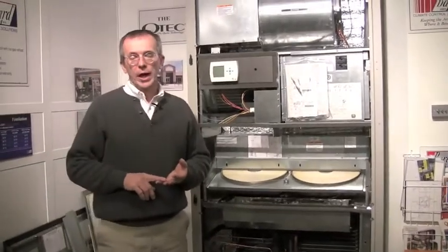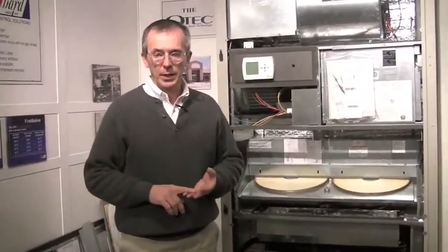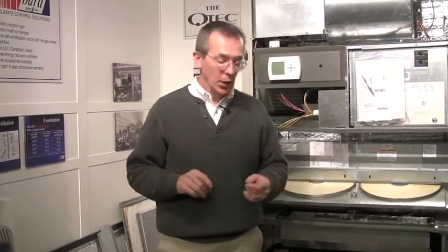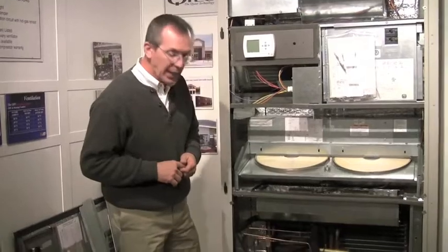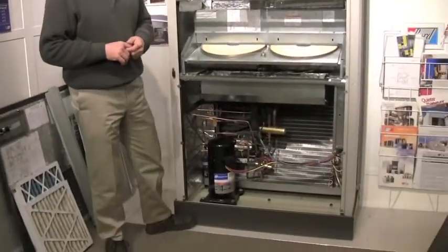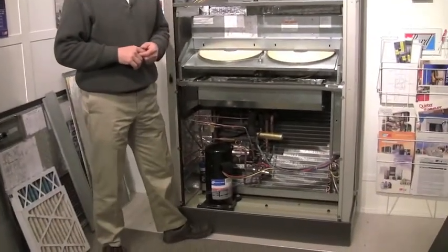Of course, the unit has to be installed with a wall sleeve. The standard wall sleeve is 14 inches thick. Once installed, there are 2 bolts that protrude out of the wall sleeve. The unit comes with heavy-duty casters mounted to it. This panel covers up those casters.